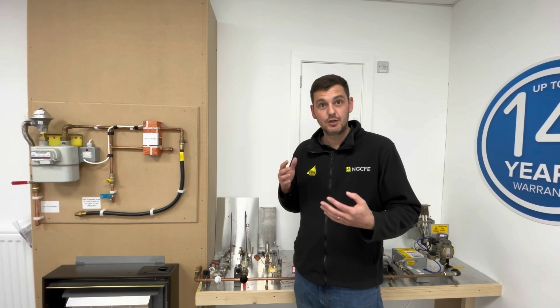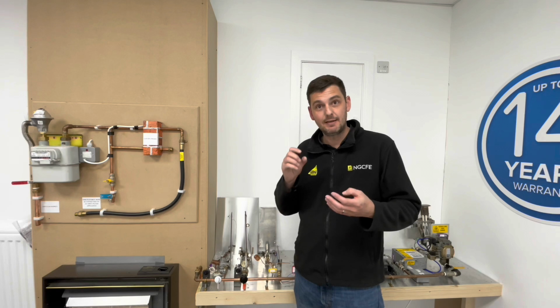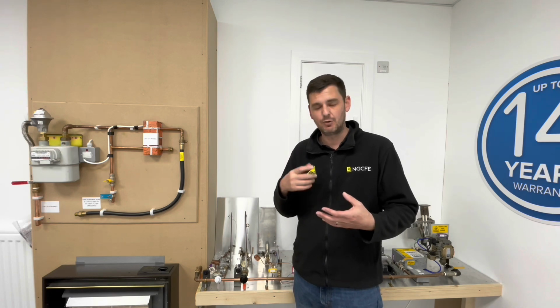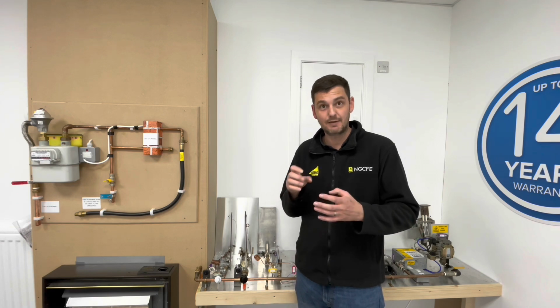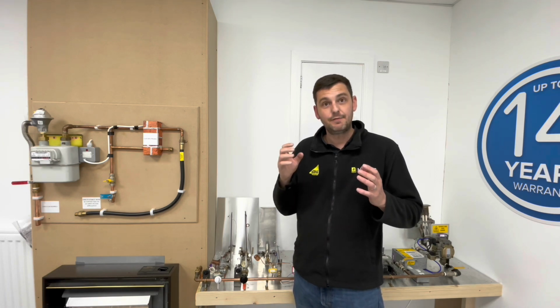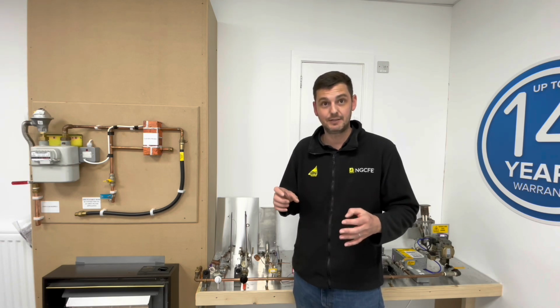Basically how it works is we fire the appliance up and the appliance lights on a low light, a small flame if you like. Now once the liquid expansion FSD gets hot, once that phial starts getting hot, the liquid expands, or the vapor expands down the capillary tube, but instead of closing a set of bellows, this time it opens a set of bellows. So if you imagine you've got your burner with a small phial inside it, the bellows in the FSD are closed, and once the phial gets hot, the vapor expands and opens the bellows, allowing a full rate of gas through. Initially it's just going through a bypass, another bypass inside the FSD.